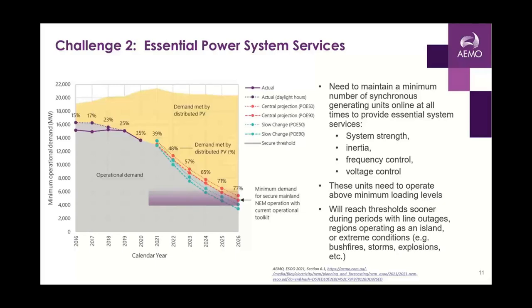And those large plants have a minimum level that they need to operate at to be able to be online. If they can't operate at a certain level, they actually have to be disconnected completely. And so we are finding that we're almost going to get to times where those levels cross, and we might need to do some actions where we need to stop having PV providing generation to us, and make sure that we can maintain those minimum levels so that the other generators are online at those times when we need it. So we're anticipating that could happen in some regions in the next few years.